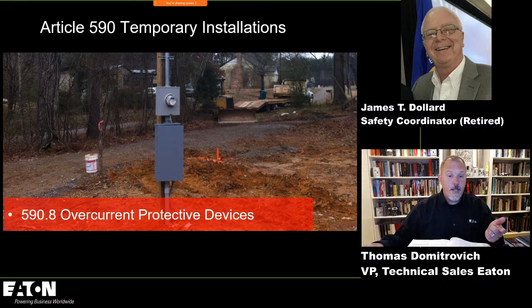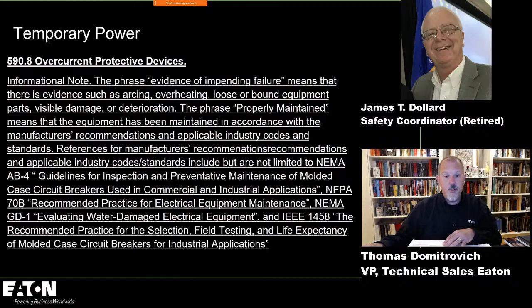And it can get to a point where, evidence of impending failure, which they added an informational note to tell us what that means, to give us some guidance on that. But that equipment can end up looking pretty ratty by the time, over the years.